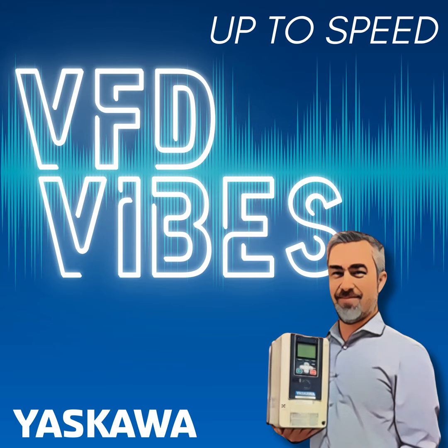So that's where we want to be very careful that we're not introducing that noise - that's why it can act like a ghost. I've been in front of a rather large piece of machinery, a multi-cell welding station. It might have been because they were in their commissioning phase, but all the networks would come up and check out fine. As soon as they would start the cell up, things would start to get flaky - sometimes it would run great, sometimes it would shut down. I went and looked inside the first panel and saw Ethernet cables draped in front of VFDs.